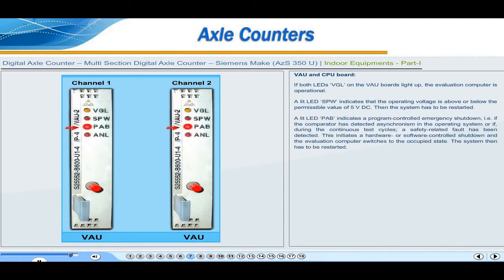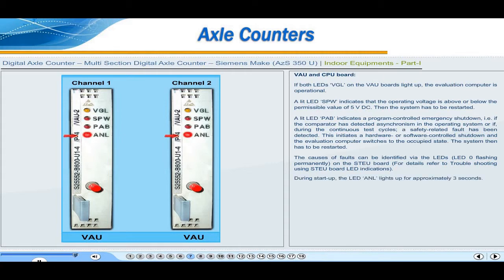A lit LED PAB indicates a program-controlled emergency shutdown. That is, if the comparator has detected asynchronism in the operating system, or if during the continuous test cycles a safety-related fault has been detected. This initiates a hardware or software controlled shutdown, and the evaluation computer switches to the occupied state. The system then has to be restarted. The causes of faults can be identified via the LEDs, that is LED 0 flashing permanently on the STEU board. For details, refer to troubleshooting using STEU board LED indications. During startup, the LED ANL lights up for approximately 3 seconds.